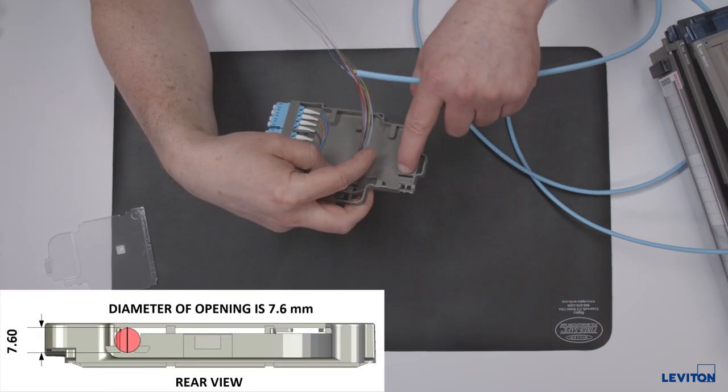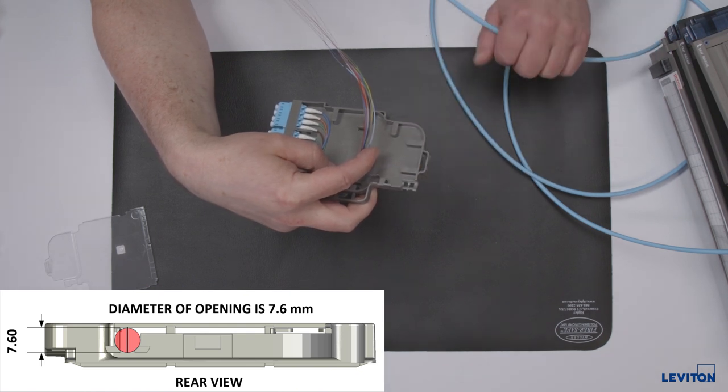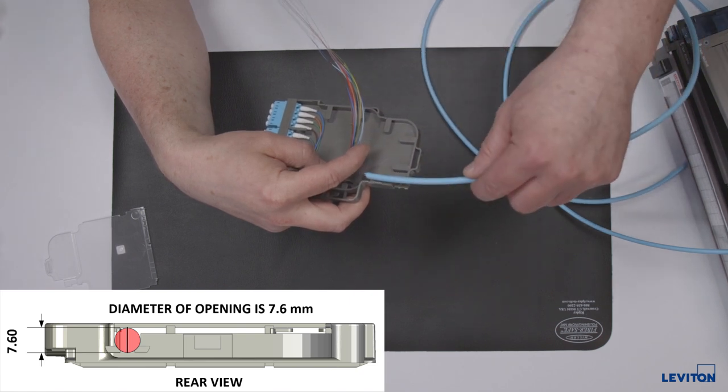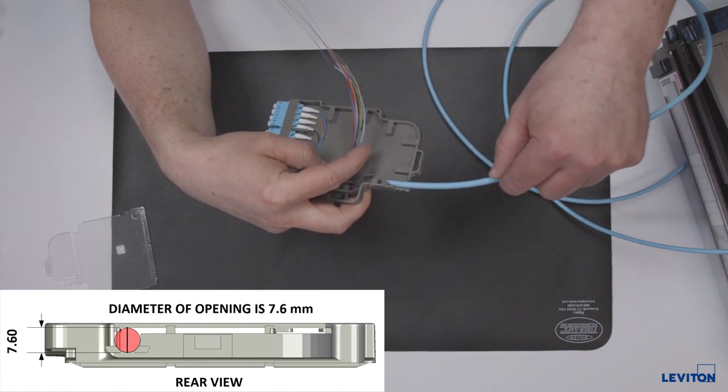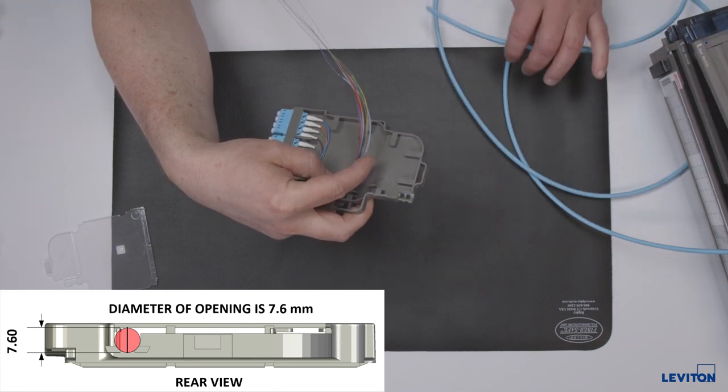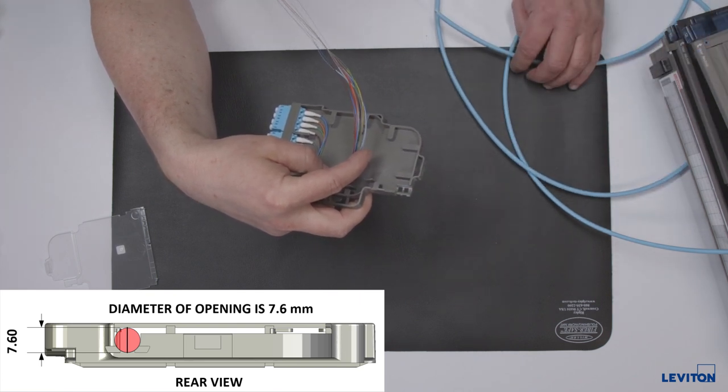The incoming cable opening at the rear of the splice module has a diameter of 7.6 millimeters or 0.3 inches. While most common 12 fiber cables have a smaller diameter, each incoming fiber should be evaluated to verify correct sizing as cable constructions do vary.